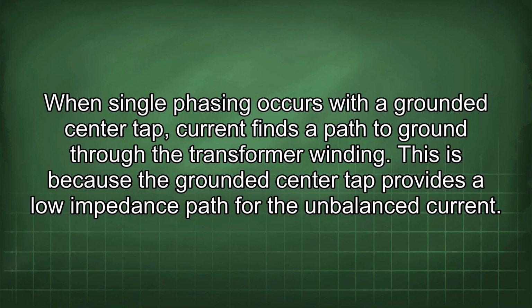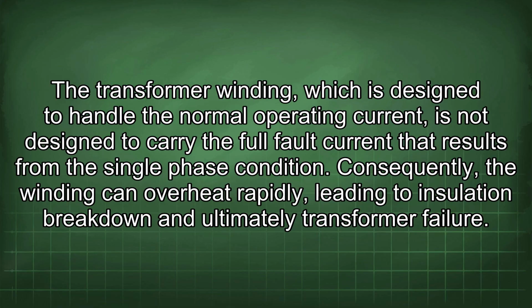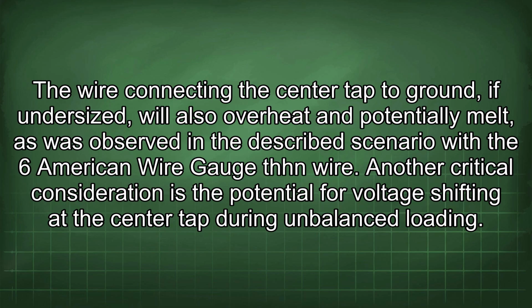When single phasing occurs with a grounded center tap, current finds a path to ground through the transformer winding. This is because the grounded center tap provides a low impedance path for the unbalanced current. The transformer winding, which is designed to handle the normal operating current, is not designed to carry the full fault current that results from the single-phase condition. Consequently, the winding can overheat rapidly, leading to insulation breakdown and ultimately transformer failure. The wire connecting the center tap to ground, if undersized, will also overheat and potentially melt, as was observed in the described scenario with the 6 American wire gauge THHN wire.